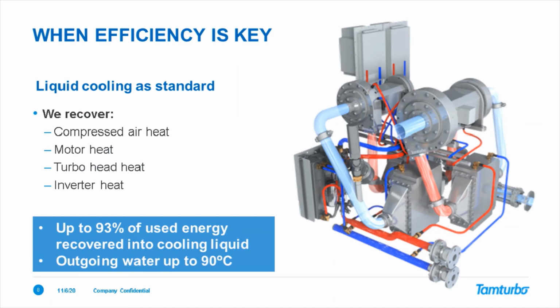So from the water, there's no contamination to the air, and of course, the cooling water itself can be fresh water, so you can use the factory fresh water and then get the heated water for the heating of the building or showers or canteen or whatever, or you can use a closed loop. We can have a closed loop circuit here if you are using, for example, river water or something else to cool it.